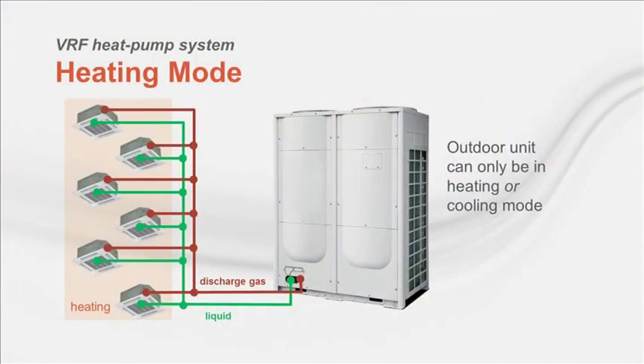For example, on a cool March morning, when people arrive at work, they generally will need heat to offset the overnight building cool down. So the system goes into heating mode and satisfies the occupants. But look what happens to the top zone and east-facing conference room with lots of glass later that morning. The occupants in the conference room want cooling, but the system is still in heating. The unit serving that conference room will not begin to cool until all the other zones are satisfied, and the outdoor unit can go into cooling mode.